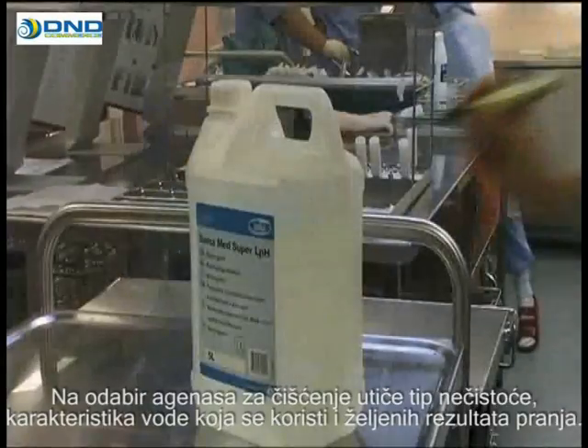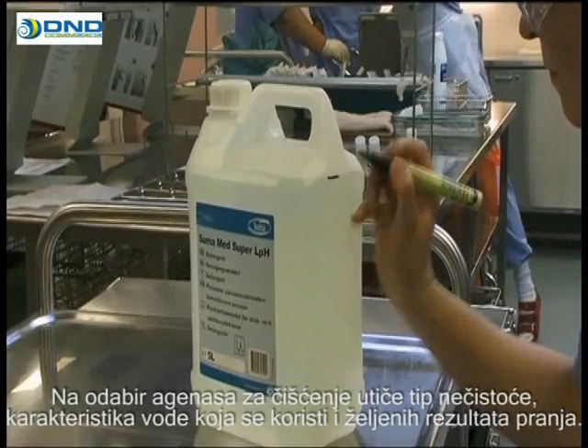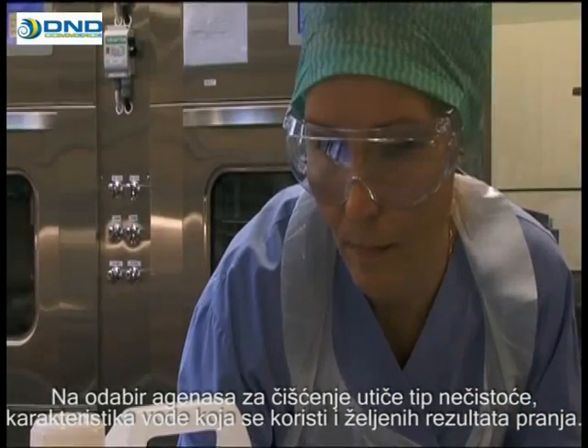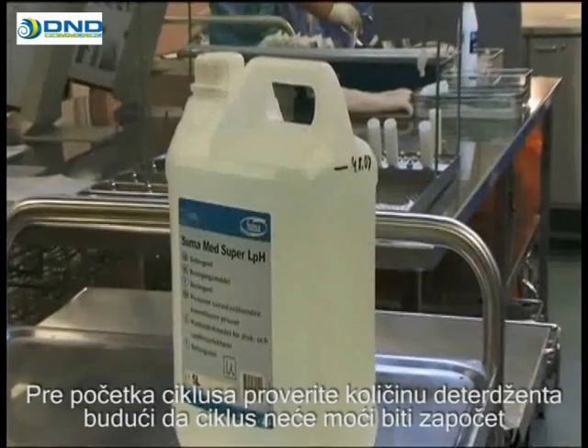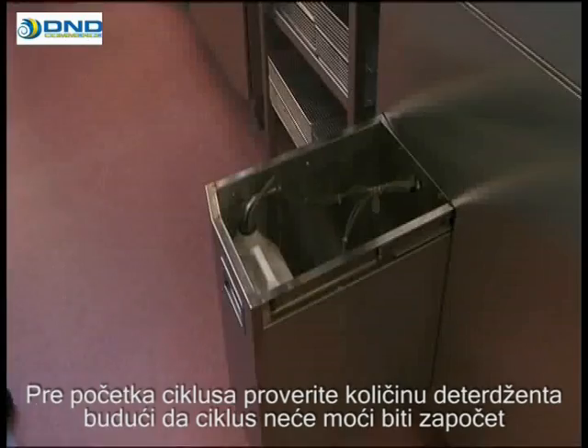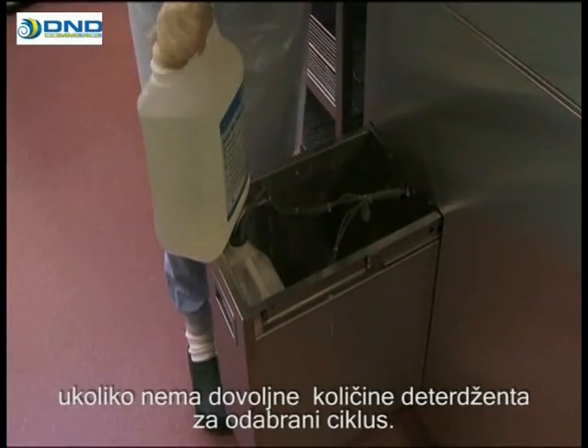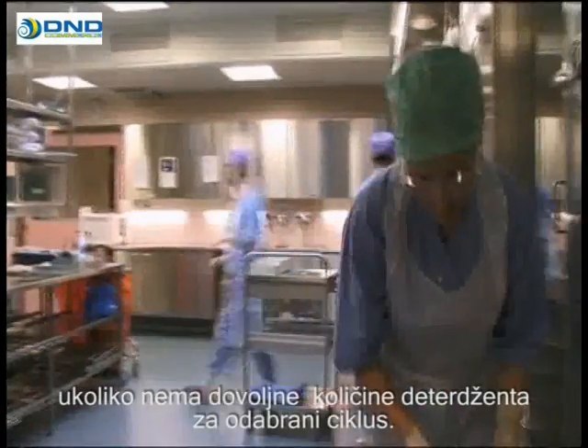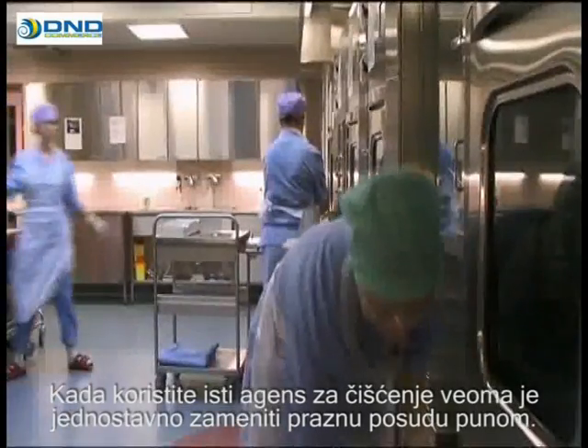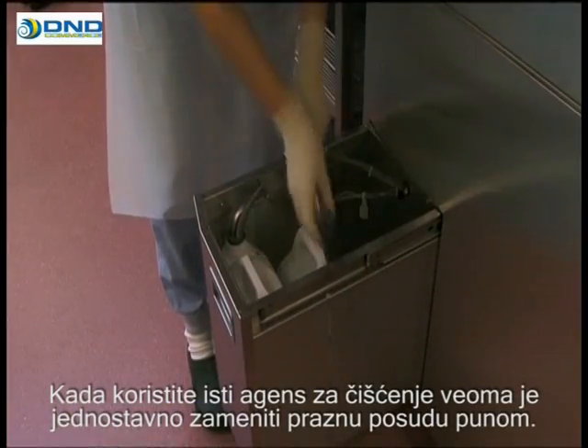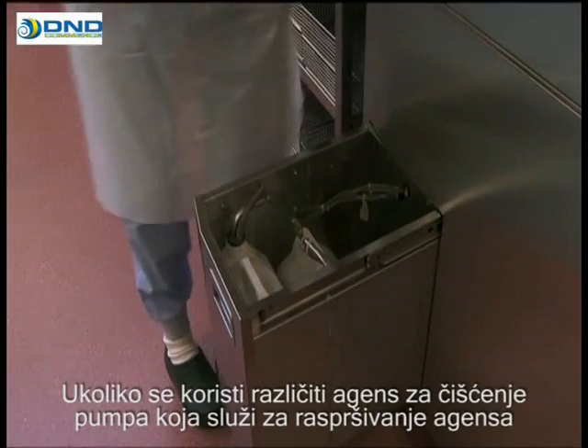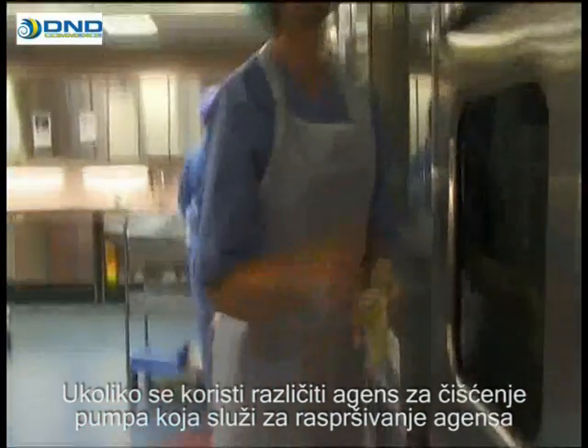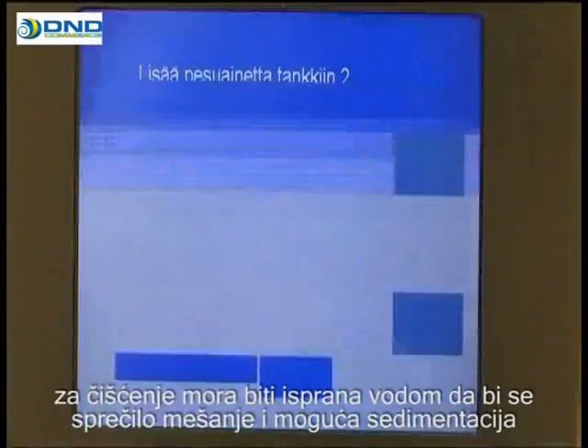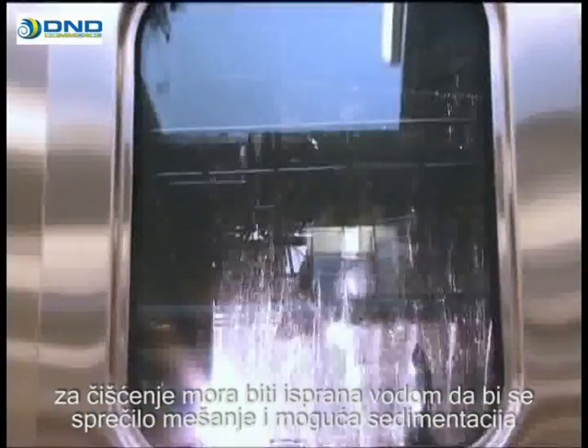The selection of cleaning agent is influenced by the type of soil, the properties of the water used, and the required washing result. Before starting the cycle, check the amount of detergent. The cycle does not start unless the volume of detergent is sufficient for the chosen cycle. When using the same cleaning agent, it's simple to replace an empty container with a full one. If a different chemical will be used, the pump dispensing the cleaning agent shall be rinsed with water in order to prevent mixing and possible sedimentation of the substance and resulting blockage in the pump. The dosage of detergent must be monitored regularly.